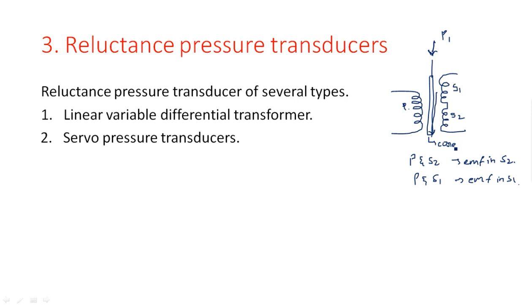That means, depending upon the direction of the applied pressure, the resultant EMF is developed in either S1 or S2. The output voltage V_out is taken as the difference V1 minus V2. One time V1 may be high and one time V2 may be high, depending upon the movement of the soft iron core. This is what the linear variable differential transformer working is.